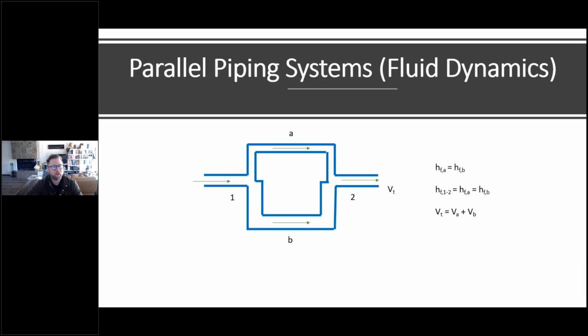Now, if we wanted more flow through A, as we discussed last time, there's a few things we could do to pipe segment B. We could reduce the size of pipe segment B. We could put a balancing valve that would introduce what I like to term an artificial pressure drop in pipe segment B, which would push more of the water into A. We could lengthen pipe segment B.